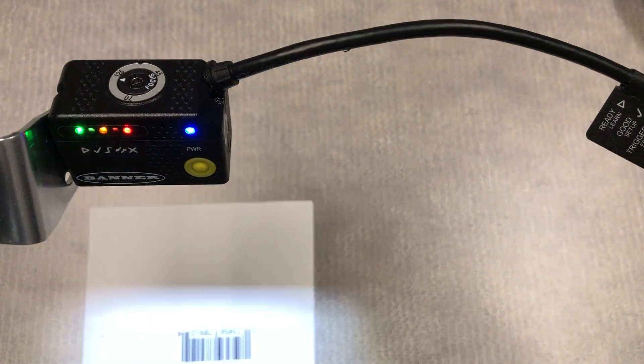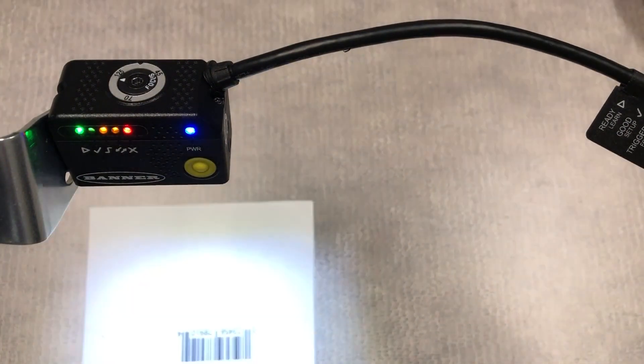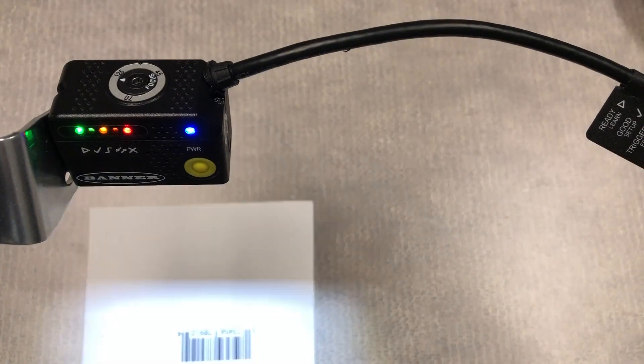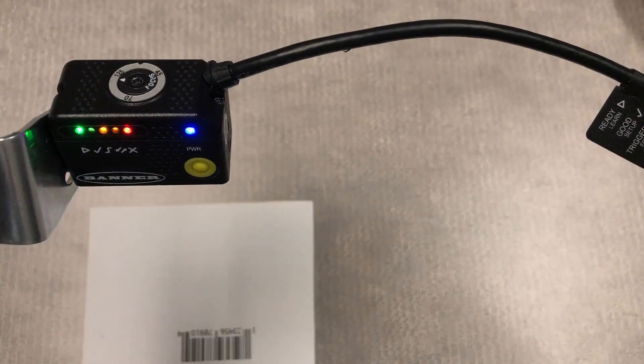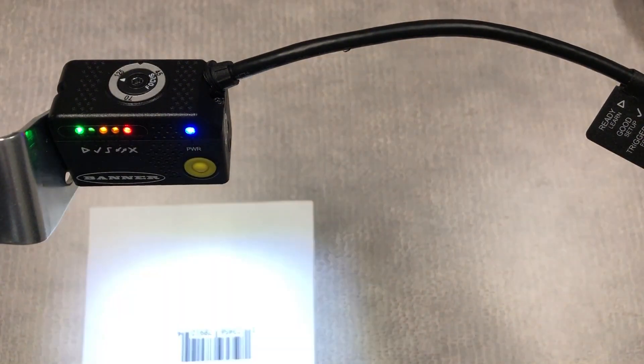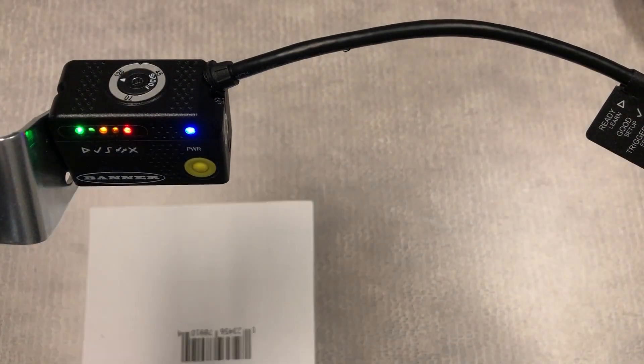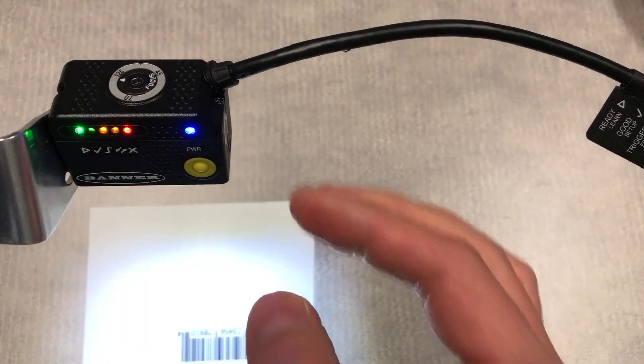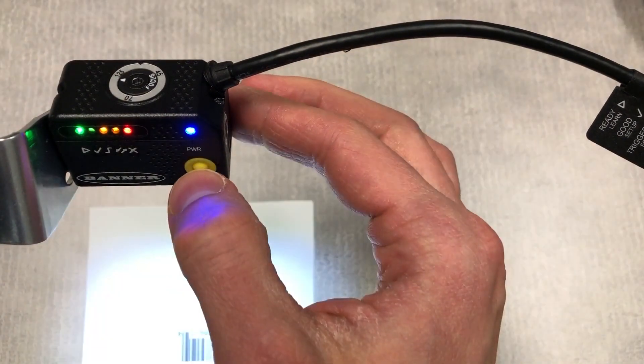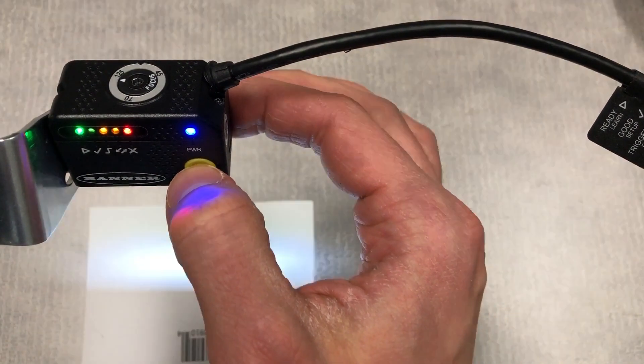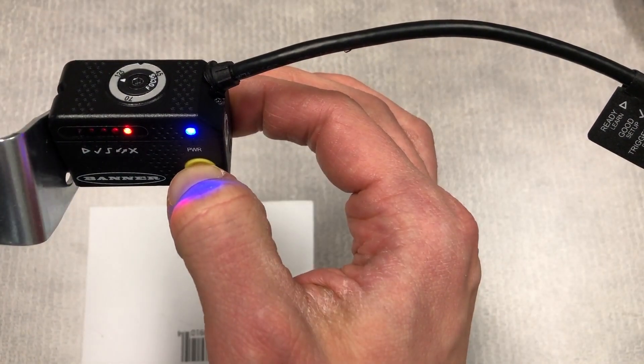The brightness has now been optimized, but it still isn't reading this barcode because it hasn't yet been configured for this barcode symbology type. We can do that with the last SmartTeach function, which is learn mode.